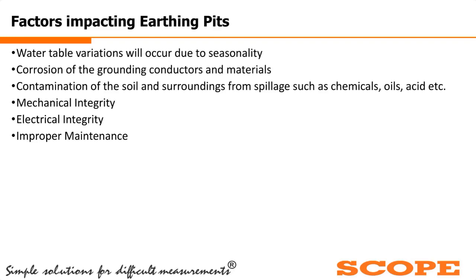And the next one is mechanical integrity. Any loose connections of the earth mats or the earth conductors will also hamper the earth pit performance. Next is electrical integrity, and the last one is improper maintenance of the earth pit. If we are not checking and maintaining the earth resistance properly as per the planned maintenance schedule, and whatever value is allowed in the organization, then this improper maintenance of the earth pit will also hamper the performance of the earth pits.